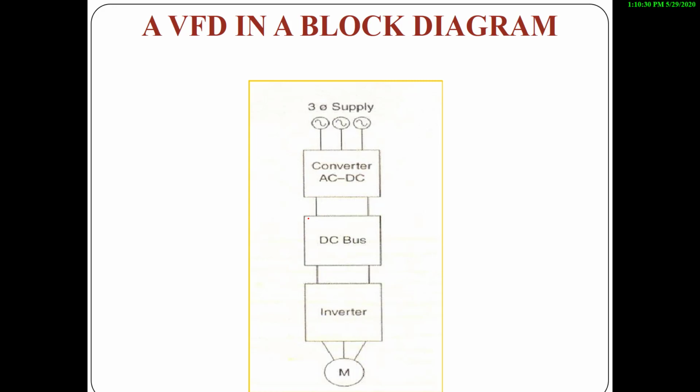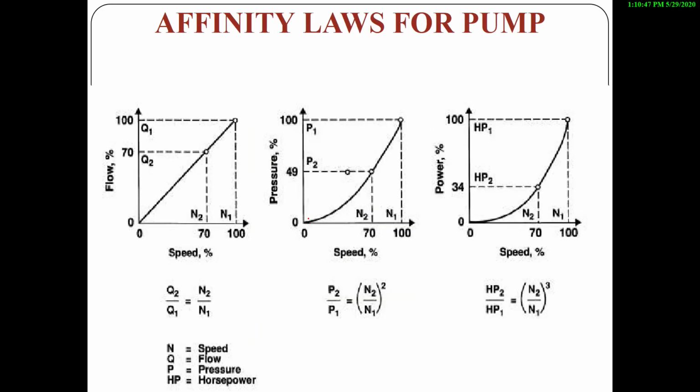VFD, we have already seen what a VFD is, that is, a variable speed drive or variable frequency drive, which is used to drive any kind of 3-phase motor in order to achieve energy savings and to reduce the cost of energy consumption. You will see what that is. This is the affinity law for a pump: Q, the flow, is directly proportional to speed N, and P, the pressure, is directly proportional to the square of the speed, and HP, the horsepower, is directly proportional to the cube of the speed.